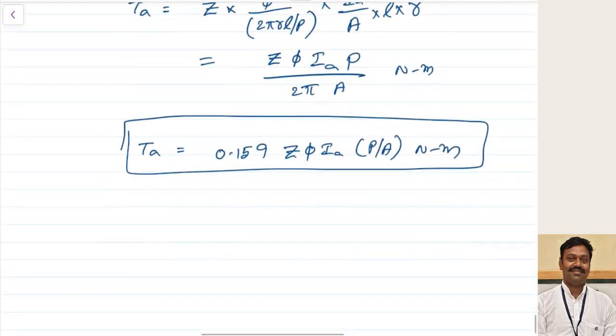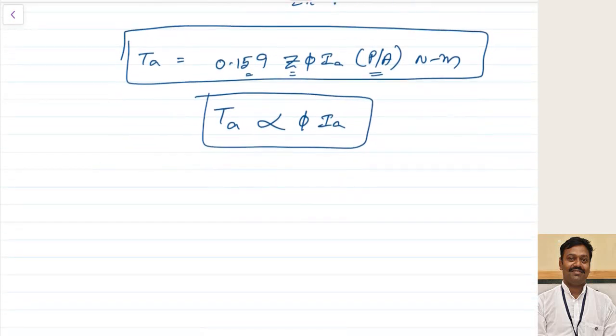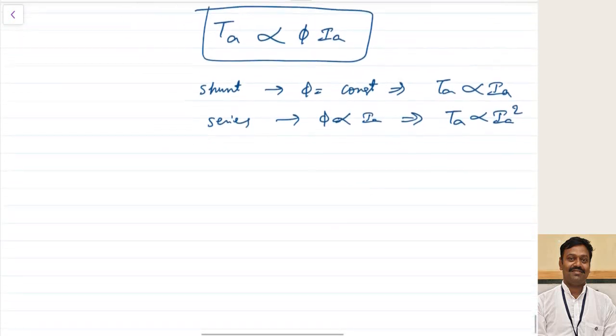This is the total armature torque. Since 0.159 is constant, Z and P/A are also fixed once the machine design is fixed, the only variables are flux φ and armature current Ia. So torque T is proportional to φ into Ia. For a shunt machine, flux φ is nearly constant, so armature torque Ta is proportional to Ia. For a series machine, flux is proportional to armature current, so torque is proportional to Ia squared.